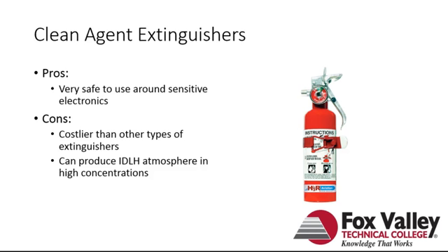It's also considerably costlier than the other types of extinguishers. And if in a high enough concentration, you can actually create an IDLH atmosphere. It's not really a portable extinguisher, but a lot of companies will have very similar fixed systems. So if there's a big fire in a server room, it just floods the room with this agent and that puts the fire out, and it doesn't damage any of the other servers around.